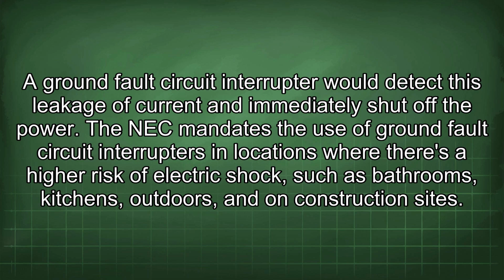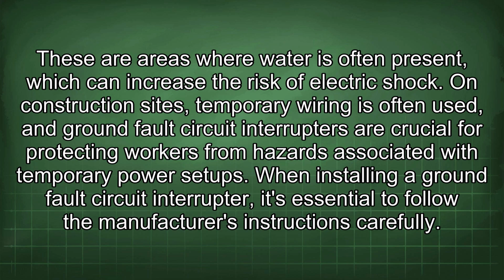The NEC mandates the use of ground fault circuit interrupters in locations where there's a higher risk of electric shock, such as bathrooms, kitchens, outdoors, and on construction sites. These are areas where water is often present, which can increase the risk of electric shock. On construction sites, temporary wiring is often used, and ground fault circuit interrupters are crucial for protecting workers from hazards associated with temporary power setups.